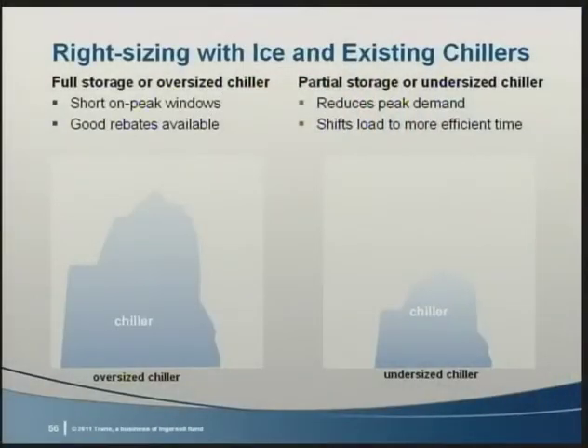But there's another benefit of an ice retrofit that is just as attractive for water-cooled systems as it is for air-cooled, and that is right-sizing using ice. Now, we normally show this graph when discussing full versus partial storage, but it also illustrates your oversized or undersized existing chiller versus the current or desired system's design day load profile.